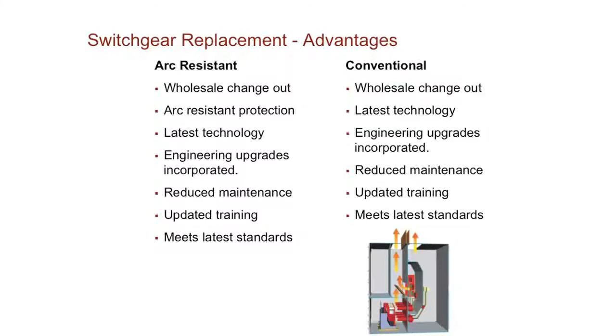And then we get into the switchgear. Again, the disclaimer is that with anything we do on the retrofit or upgrade of the equipment, you'll never get to an arc-resistant situation. There are some exceptions. We can basically get you to 25 kA Type 1 arc-resistant gear on a 5HK lineup. That's the exception. For the rest of the gear out there, there probably isn't any engineered option to this day. But the majority of people would probably say, well, for 10 or 15% more, I'll go with the arc-resistant gear. It just makes sense.